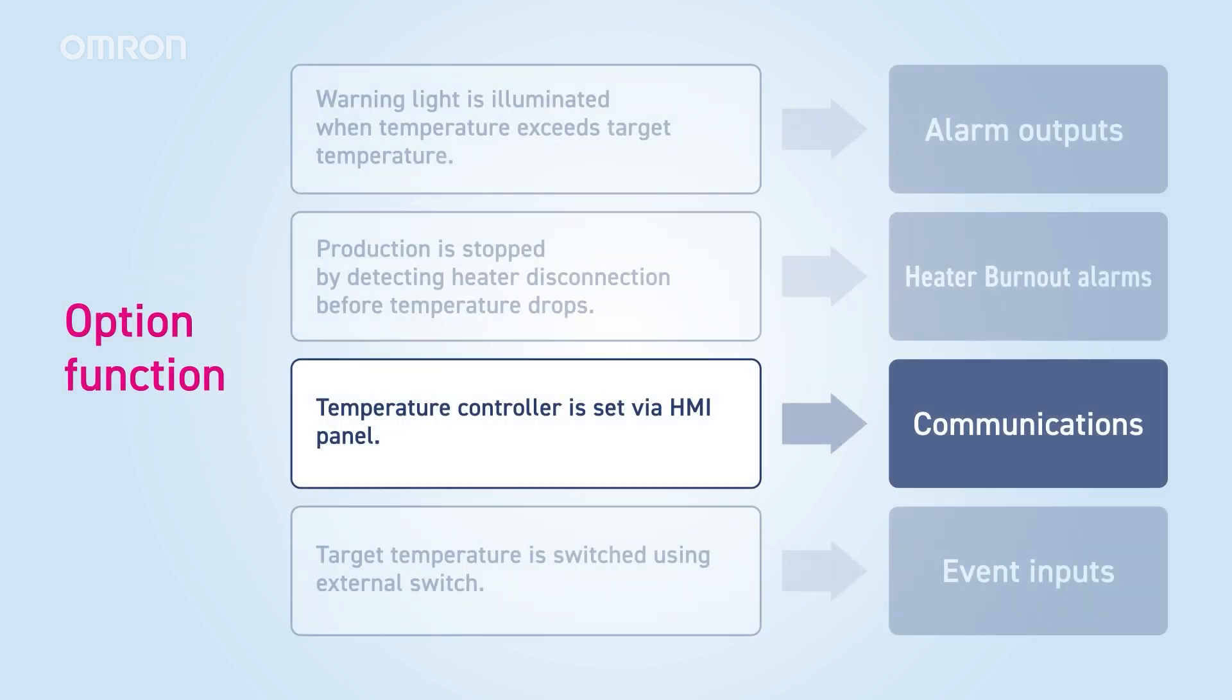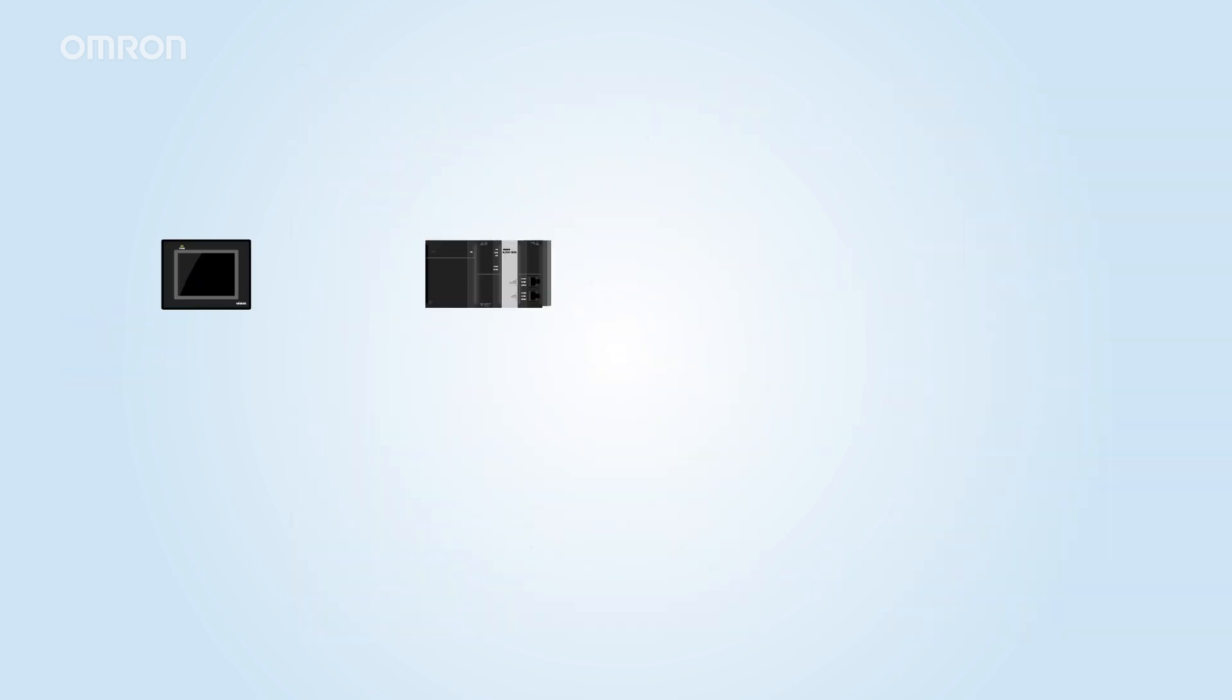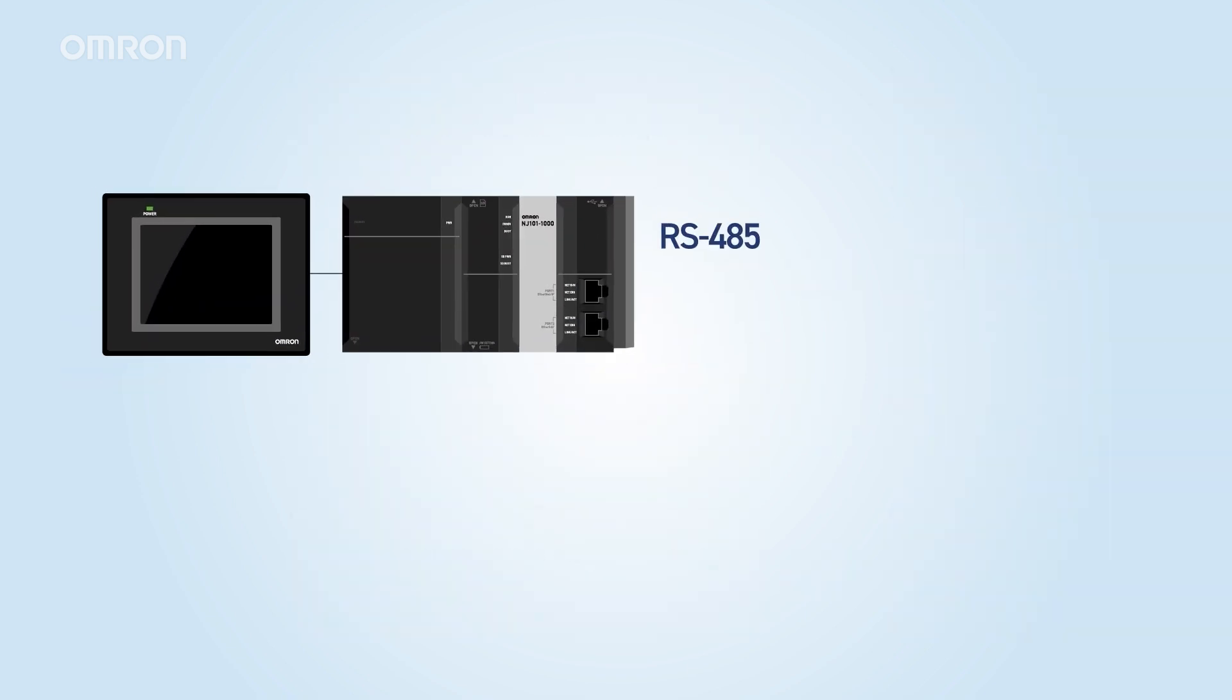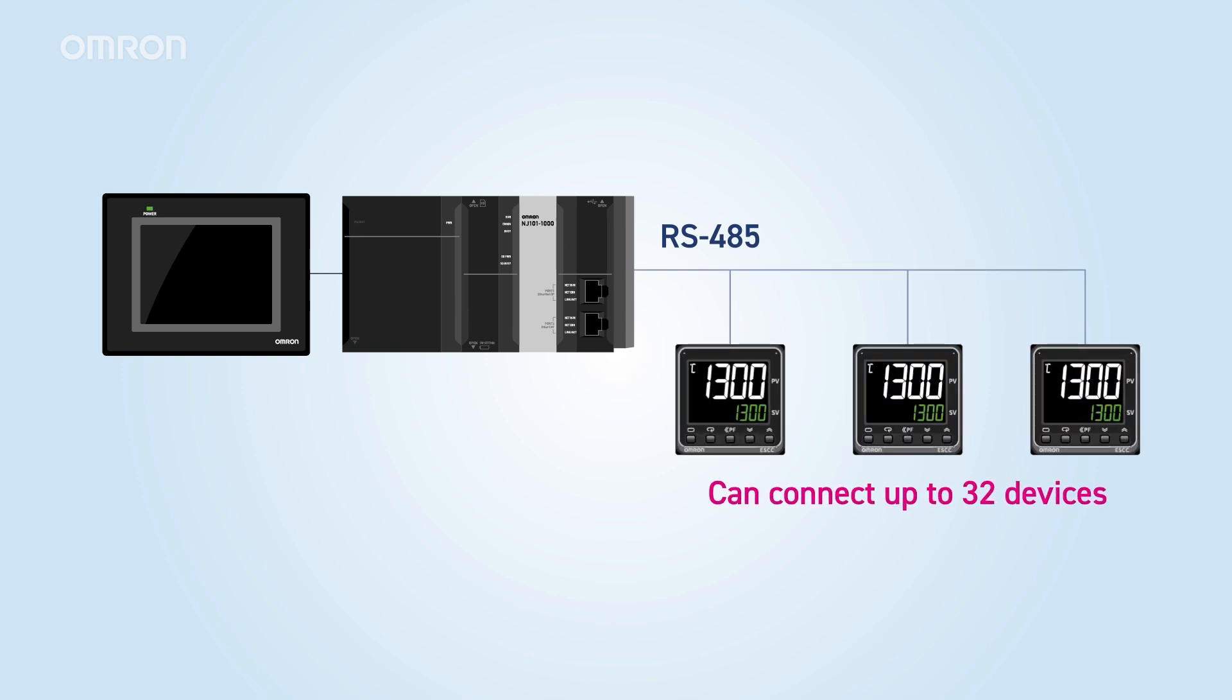Next, the temperature controller can communicate with a higher-level device. Our temperature controller, E5CC, uses RS-485 communication. By connecting the HMI panel and temperature controller through a PLC, you can set like target temperature and PID and issue operation commands such as run-stop.